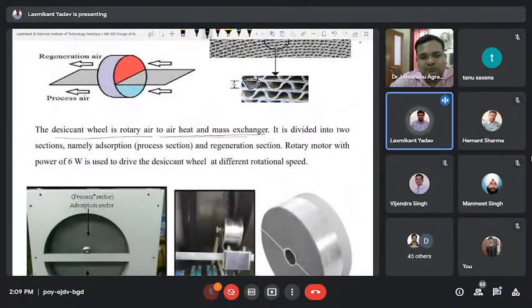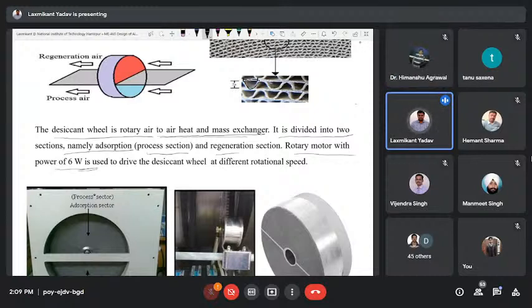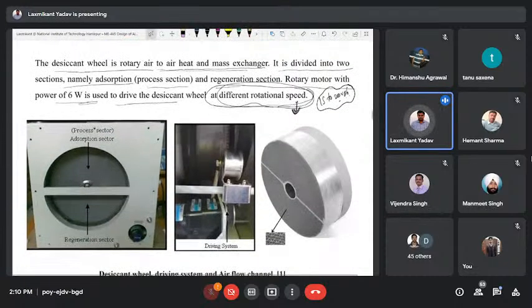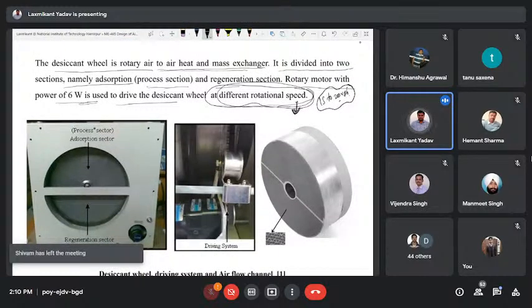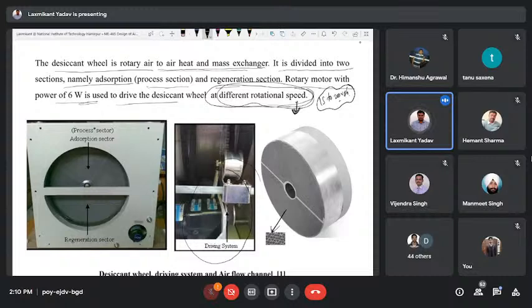Generally, it is divided into two sections, namely the adsorption section or process section, and the regeneration section. A rotary motor with a power of 6 to 10 watts is used to drive the desiccant wheel at different rotational speeds. One of the key features of the desiccant wheel is the rotational speed, which is very low, around 15 to 20 rph. This is the optimum rotational speed, in revolutions per hour, that is, 20 revolutions in 1 hour. Okay, so this is the front view. You can see the adsorption section and regeneration section, the driving system, and the sinusoidal flow channel indicated in the zoom.